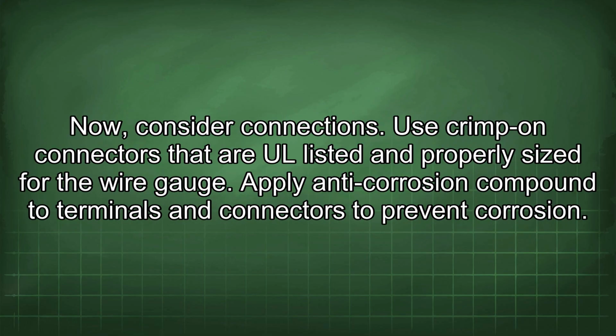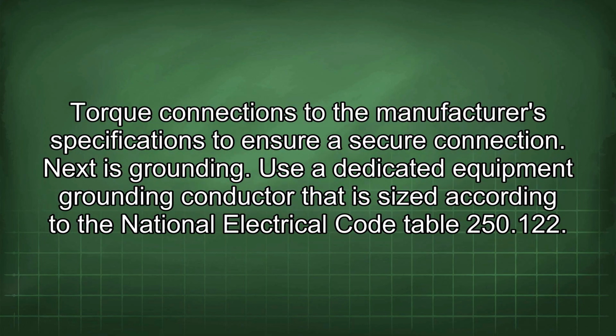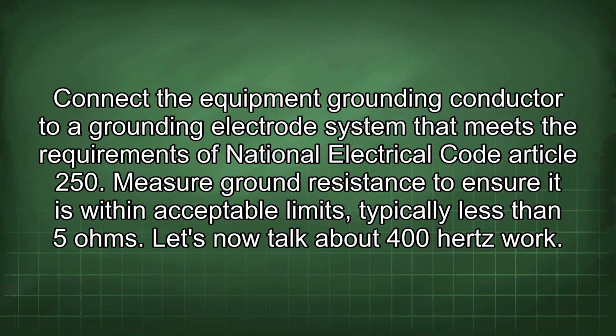Now, consider connections. Use crimp-on connectors that are UL listed and properly sized for the wire gauge. Apply anti-corrosion compound to terminals and connectors to prevent corrosion. Torque connections to the manufacturer's specifications to ensure a secure connection. Next is grounding. Use a dedicated equipment grounding conductor that is sized according to the National Electrical Code Table 250.122. Connect the equipment grounding conductor to a grounding electrode system that meets the requirements of National Electrical Code Article 250. Measure ground resistance to ensure it is within acceptable limits, typically less than 5 ohms.